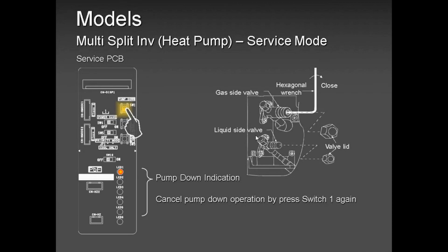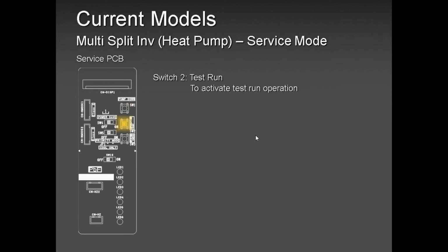But before you do that, make sure you have locked or closed the liquid line. What happens during pump down? The pump down normally is no more than 15 minutes. It all depends on job site to job site. The longer the pipe, the longer it takes to pump down. The shorter the pipe, the shorter it takes.